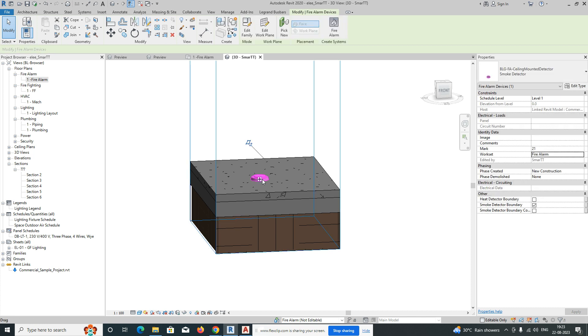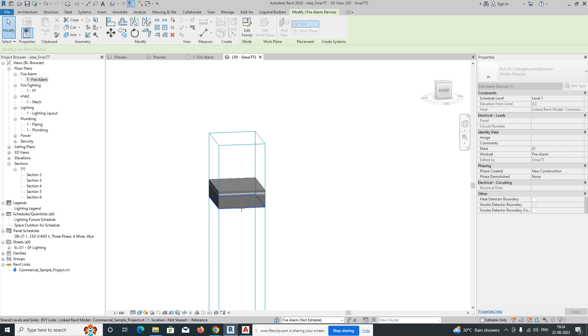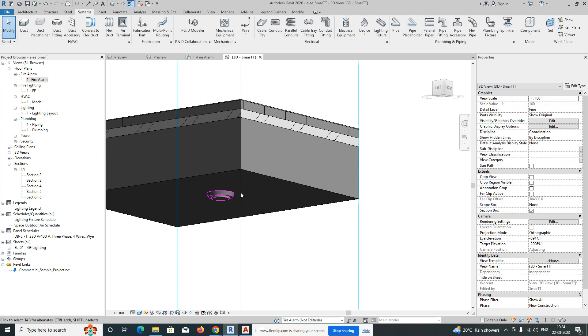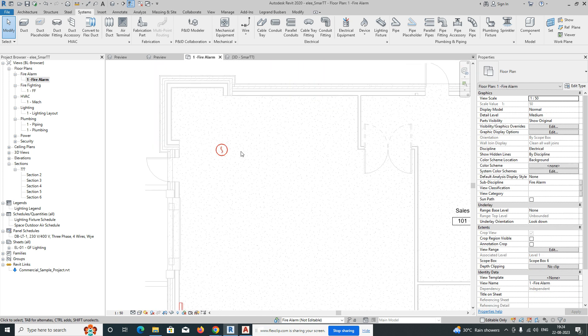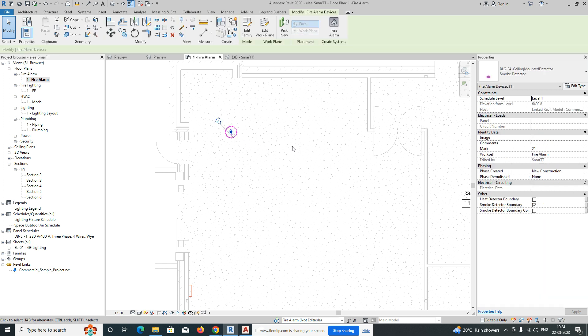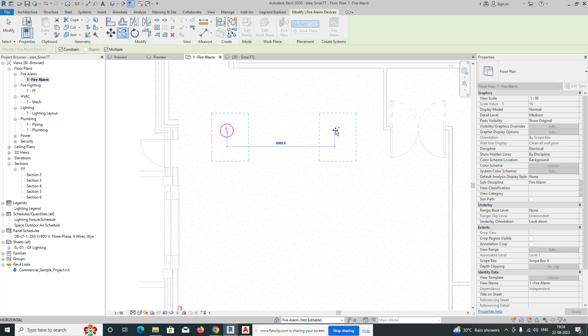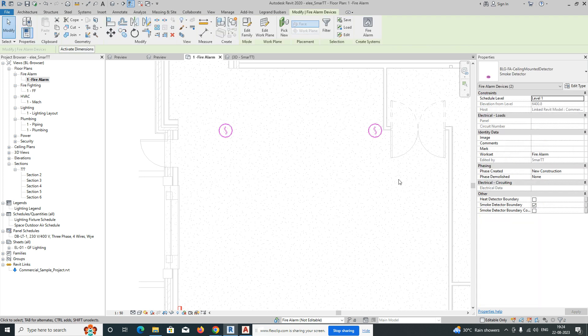We need to fix the smoke detector in the ceiling. Select the fire alarm device, go to Edit Work Plane, pick a plane, and select the ceiling. Flip it so the smoke detector faces downward — you can now see it on the ceiling. For spacing, the maximum distance is around eight meters; here we can give approximately five thousand millimeters. So we have two smoke detectors placed.